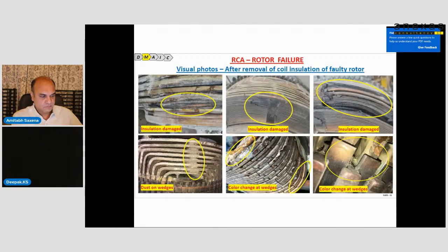Yes, once we decided that there is an interturn short in the rotor, we decided to remove the coil insulation from the faulty rotor. You can see some of the photographs of the insulation damage. When we removed the insulation from the rotor, we could see this insulation damage. These are some of the slides which show the insulation damage.